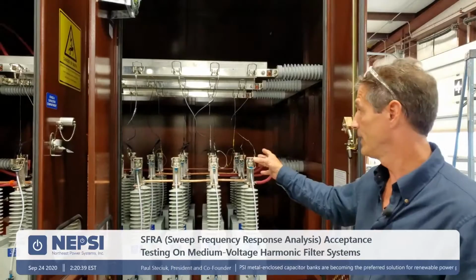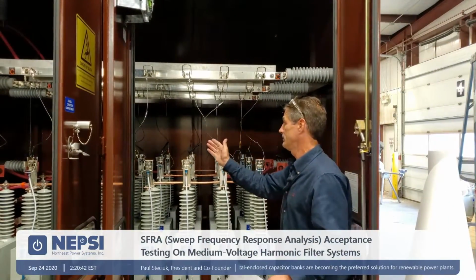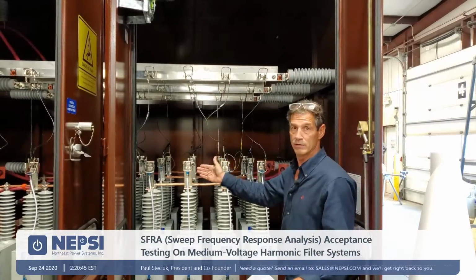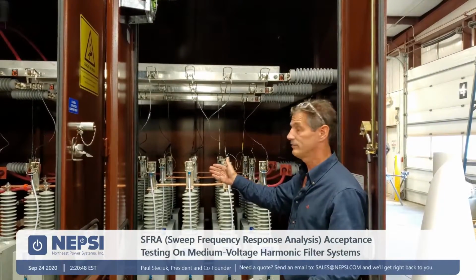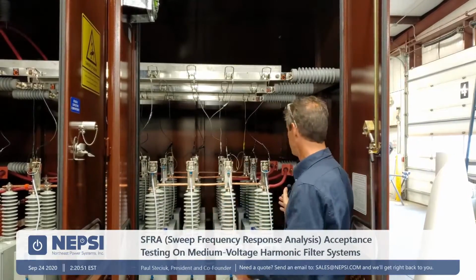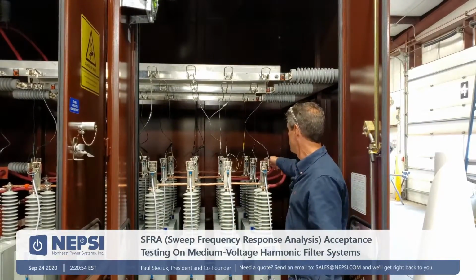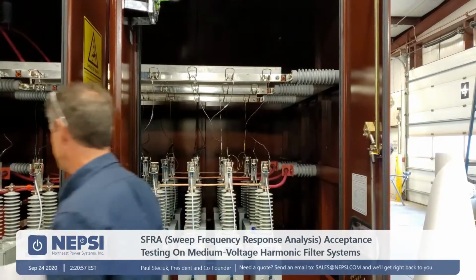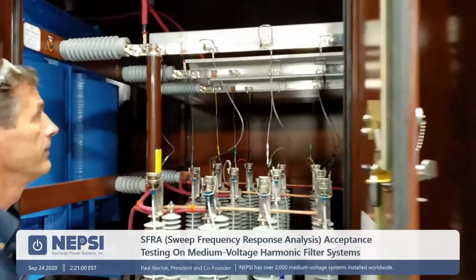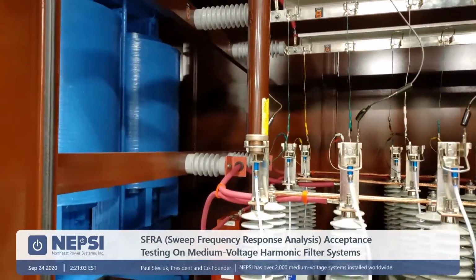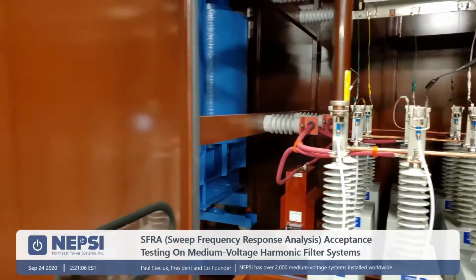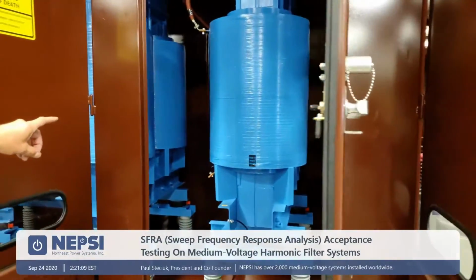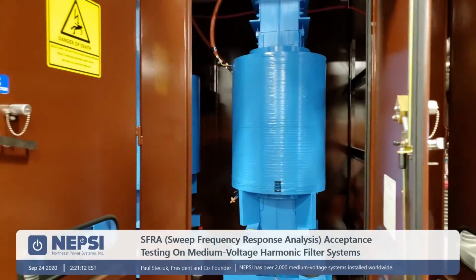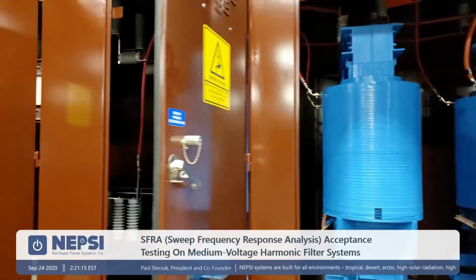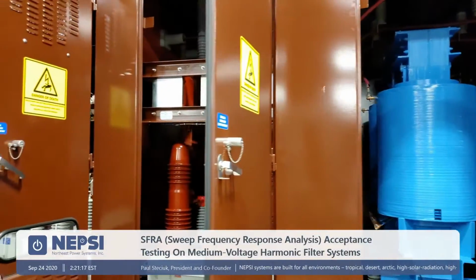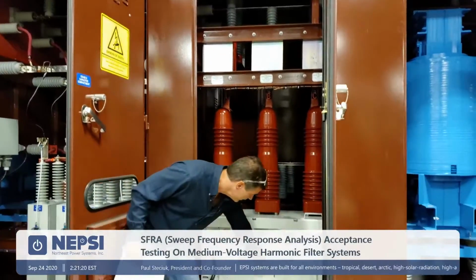All the capacitors have been connected. In this one, there's a total of 24, 8 total per phase. There's a split Y, so it's 4 on one side of the Y, 4 on the other side of the Y. The neutral here is connected on this end, and then the neutral on the other side of the Y is connected on this end. The capacitors all get fed from some harmonic filter reactors. The harmonic filter reactors are supplied by a breaker. We have already closed the breakers, so we're indicating that the breaker is closed.